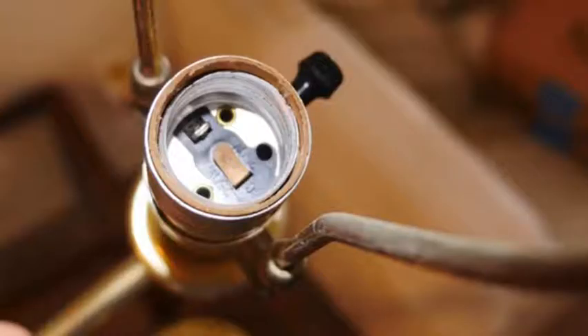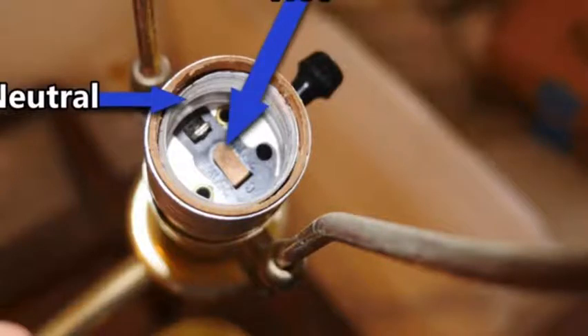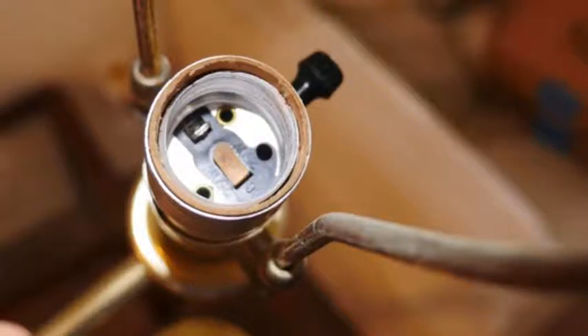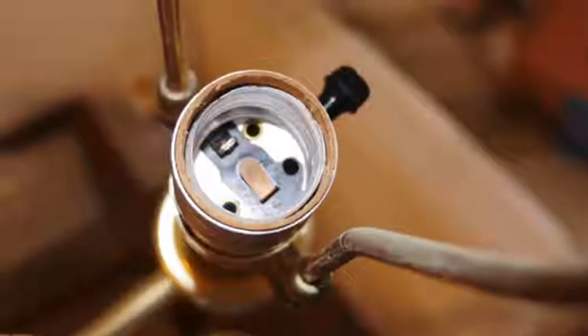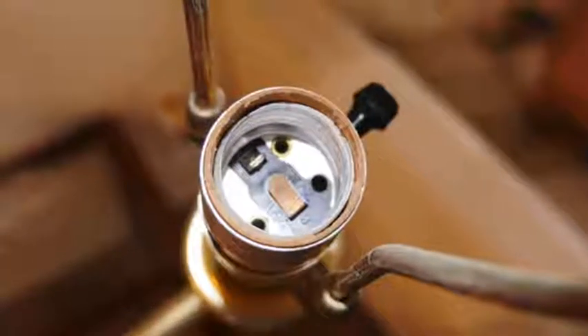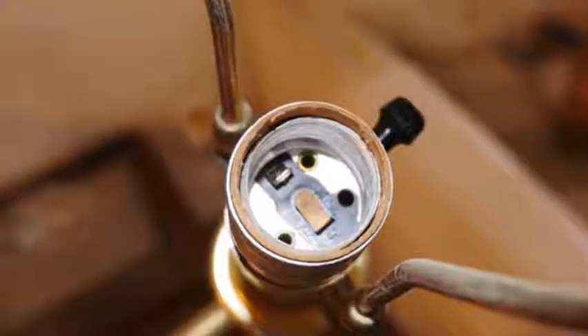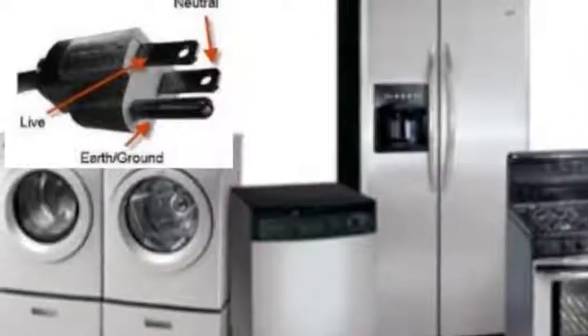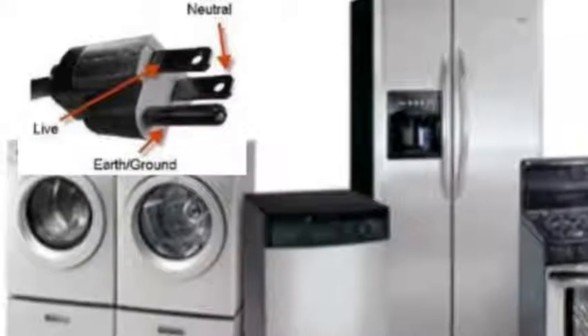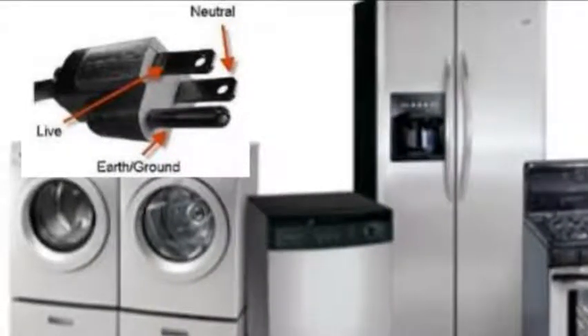To give you a really common example, let's examine this light socket. The tab on the bottom of the light socket is supposed to be the hot terminal, and the side of the light socket where you screw the bulb in is supposed to be your neutral terminal. Now, if you plug your polarized plug into a reverse polarity receptacle, all of a sudden the tab on the socket is now your neutral terminal, and the side where you screw the light bulb in is now your hot terminal, and this increases the chance of shock. The light will still go on, but now there is increased danger for the users. In particular, appliances that have circuit boards may not last as long if plugged into reversed polarity outlets.